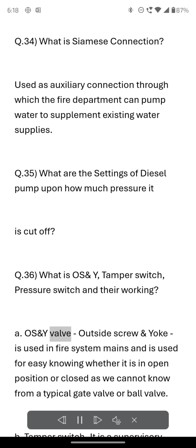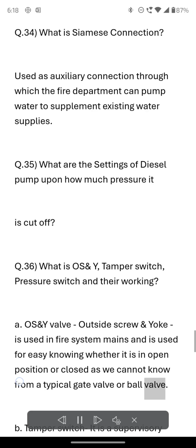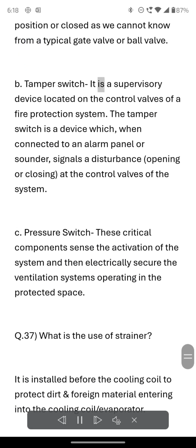A. OS and Y valve, outside screw and yoke, is used in fire system mains for easy knowing whether it is in open position or closed, as we cannot know from a typical gate valve or ball valve. B. Tamper switch. It is a supervisory device located on the control valves of a fire protection system. The tamper switch is a device which, when connected to an alarm panel or sounder, signals a disturbance, opening or closing, at the control valves of the system. C. Pressure switch. These critical components sense the activation of the system and then electrically secure the ventilation systems operating in the protected space.